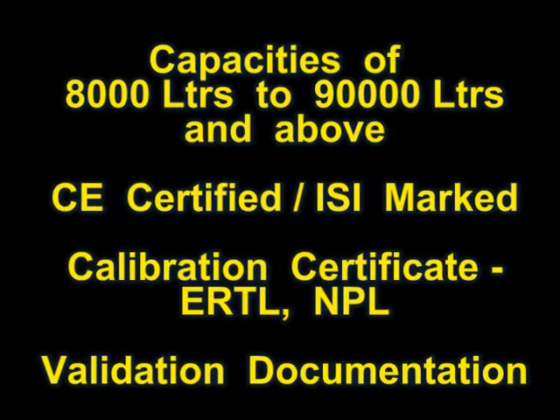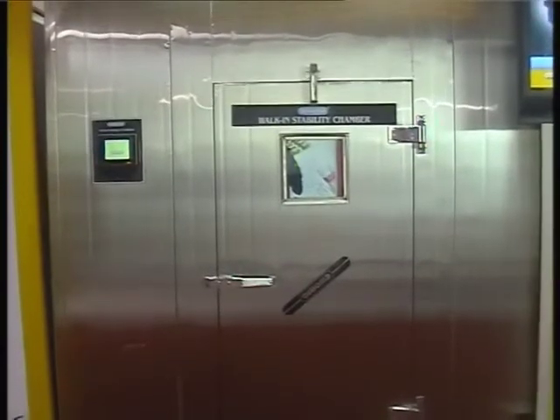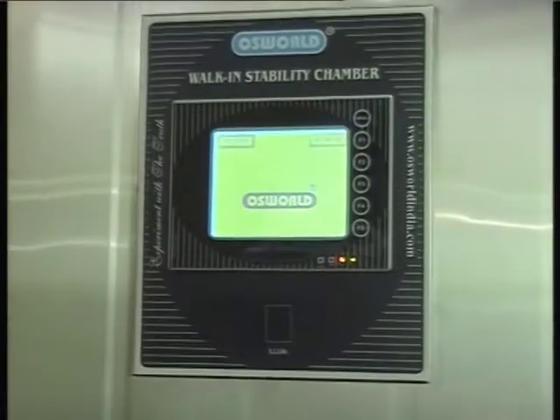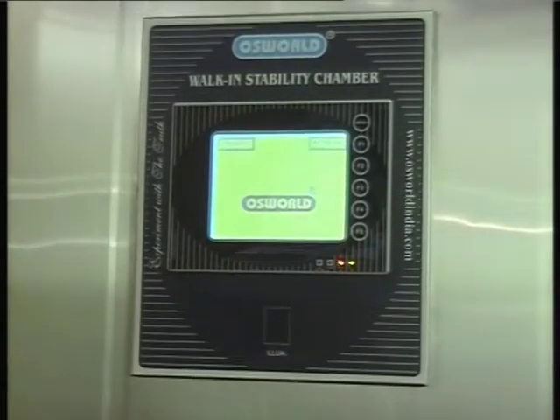The OSWORLD Walk-In Stability Chamber has a modular double-walled construction which can be assembled or erected at site. The walls are made of stainless steel with puff insulation in between walls. Heavy-duty SS wire rod trays allow passage of air and help maintain a high level of uniformity.